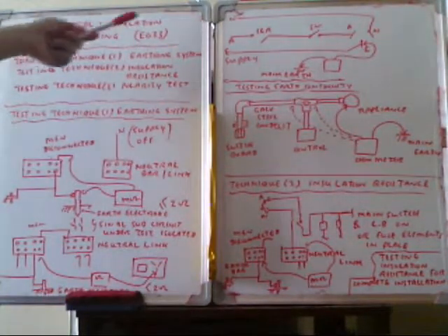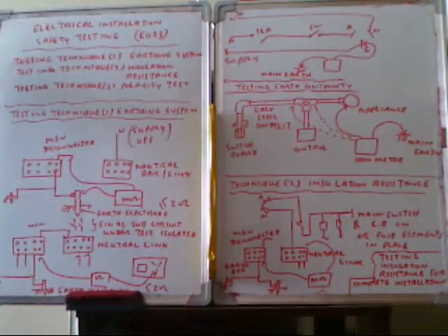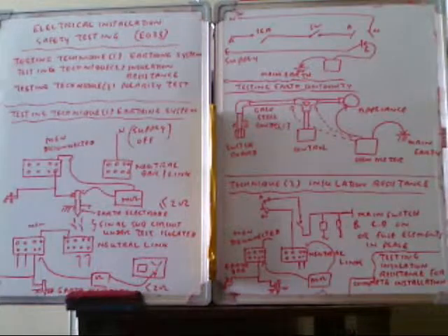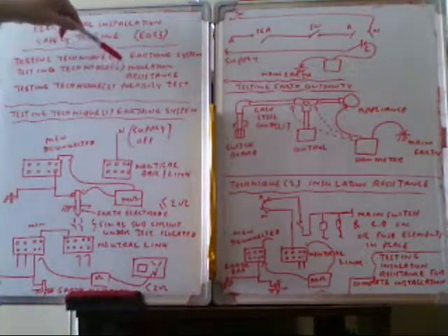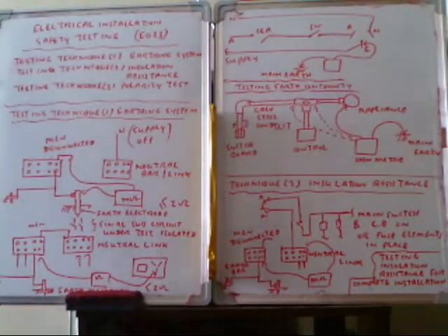Those leakages are electrocution hazards, so the leakage can be diverted to the earthing system. Leakage needs to be diverted to the ground. So the earthing system has to be tested. In the meantime, the insulation resistance between the active conductor and neutral conductor, and the active conductor and earth conductor should be tested. And also the active conductor to the ground point you have to test.